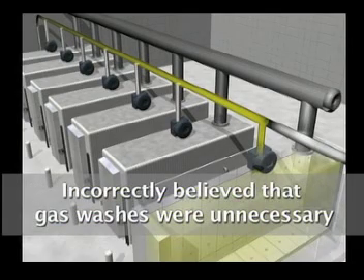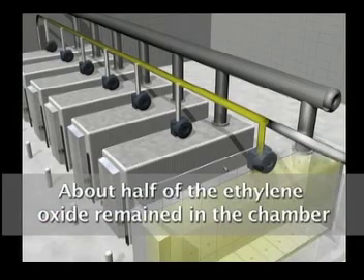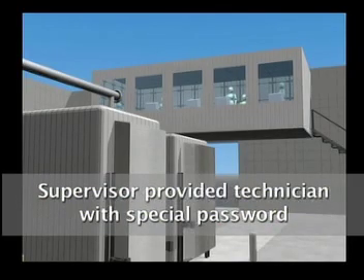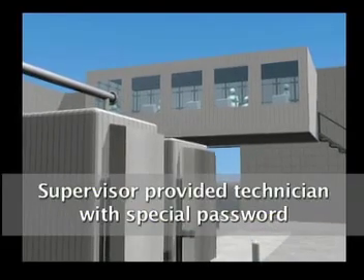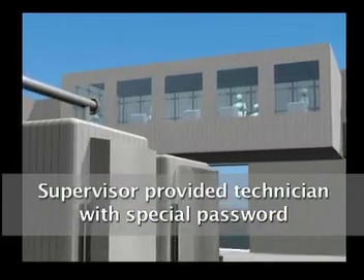All of them incorrectly believed that because there were no products in the chamber to absorb ethylene oxide, all the gas would be removed in the first step, making the gas washes unnecessary. They did not realize that about half of the ethylene oxide originally injected still remained in the chamber. There was no monitoring system to alert them to this explosive concentration of gas. The supervisor provided a technician with his special computer password to manually advance the cycle, bypassing the gas washes.